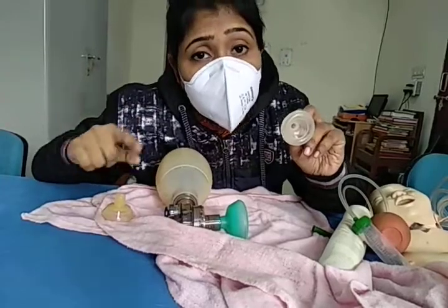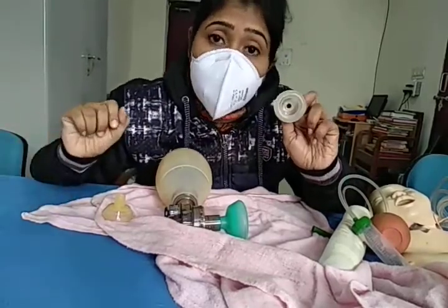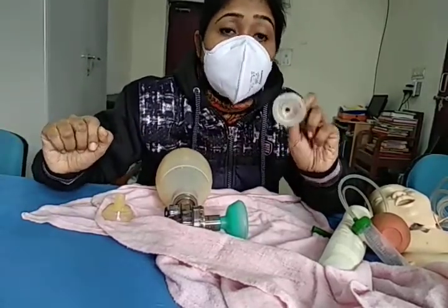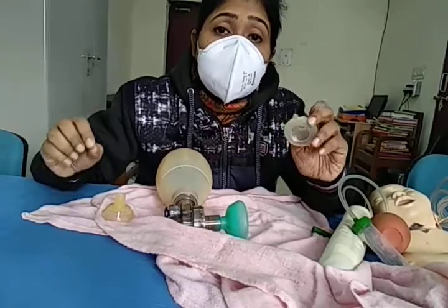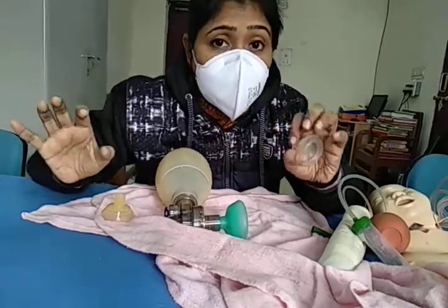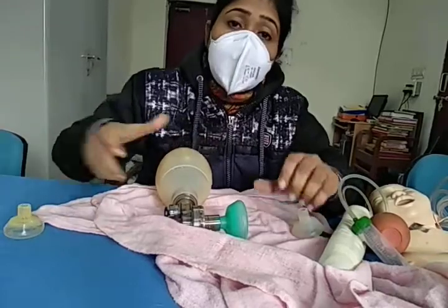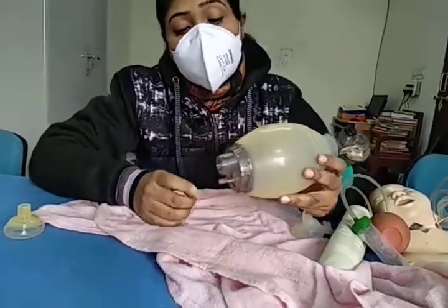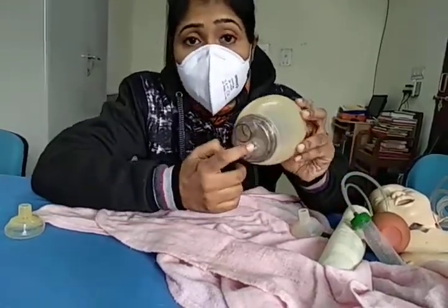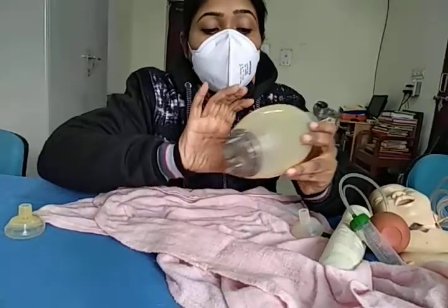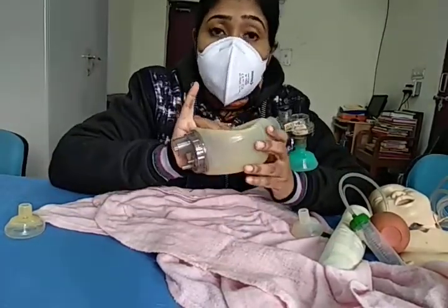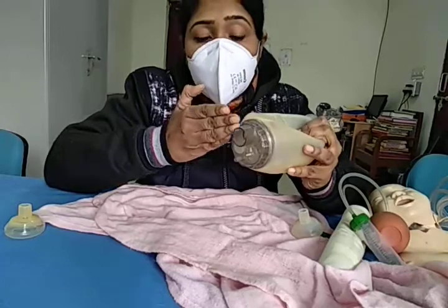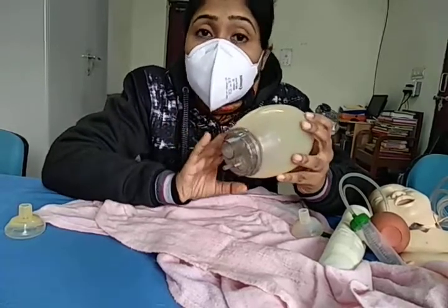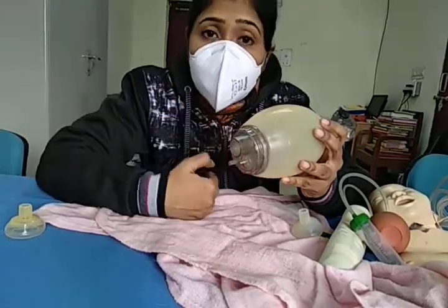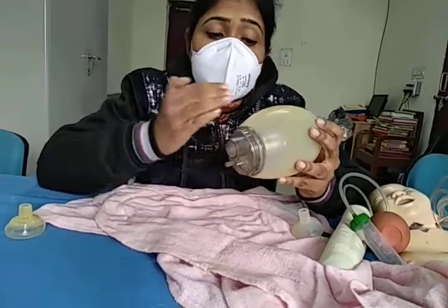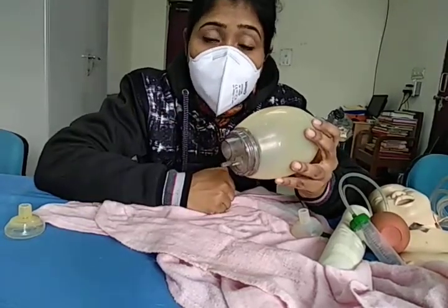Shape may also be of 2 types, circular and anatomical. The circular one is preferred because it gives a proper seal. Now the AMBU bag has 4 valves. At the back it has the inlet valve. So when we press the bag, the inlet valve closes, and when we release the bag, the inlet valve opens and allows the air to enter inside the bag.